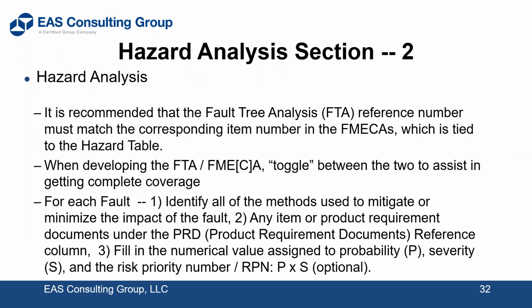So the hazard analysis is the key document that may have 10, 15 key areas or whatever that your product can cause a hazardous situation in the field. But then from that, you explode it into all the other ones, in my case a fault tree analysis and the FMECA or FMEA. So when I'm developing that, I have the hazard list pretty well locked in. And then I develop the FTA and the FMECAs back and forth. That may cause me to add something to the hazard analysis, but usually it doesn't. It's pretty complete. But it may definitely cause things to adjust between my FTA and my FMECAs.